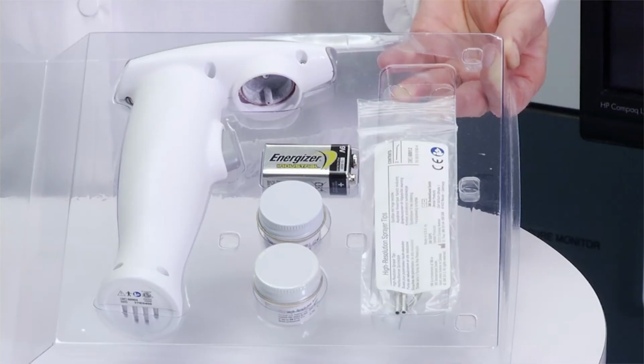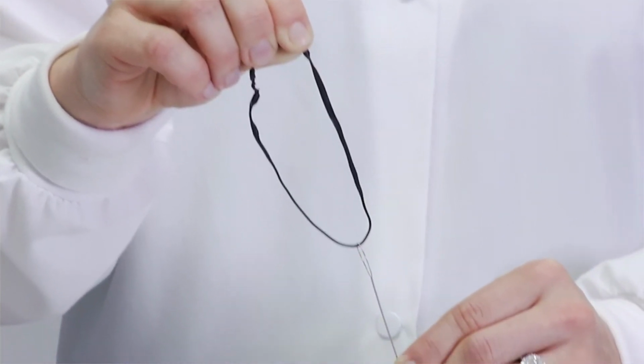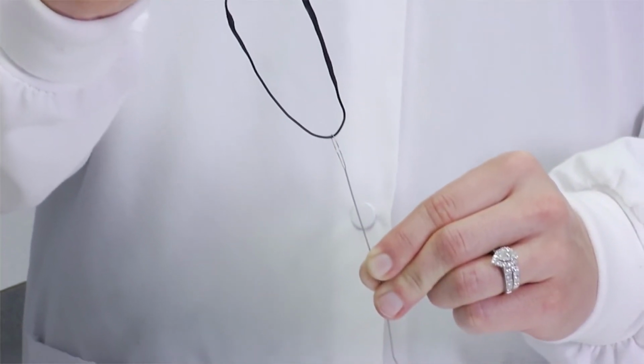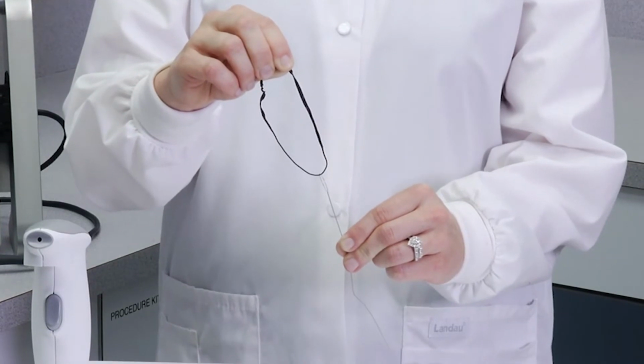Within your kit, you've been provided with 6 sprayer tips and 3 wire brushes. Being that the wire brushes are so small and can be easily lost, it is best practice to tie a string around the loop at the end of the brush and hang or place in a secure location within your sterilization or designated room.